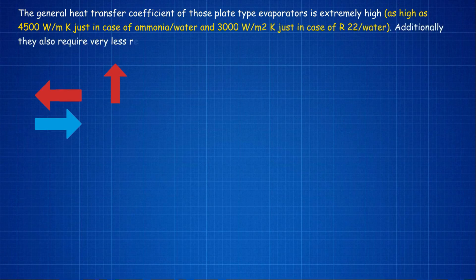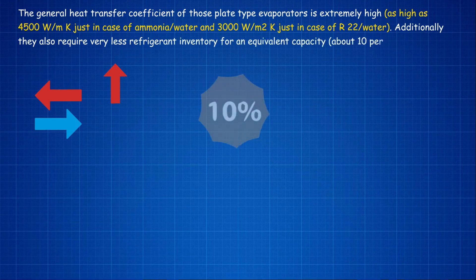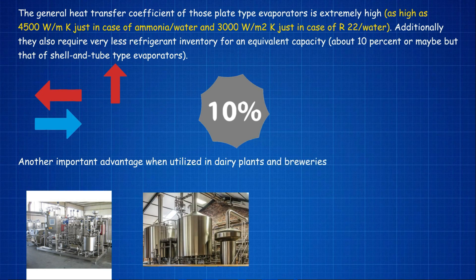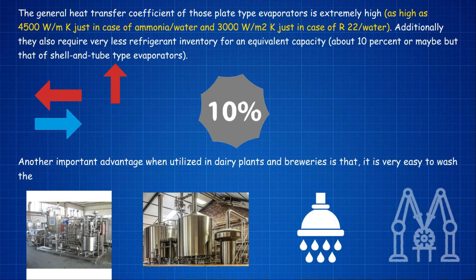Additionally, plate type evaporators require very less refrigerant inventory for an equivalent capacity — about 10% or maybe less of that of shell and tube type evaporators. Another important advantage when utilized in dairy plants and breweries is that it is very easy to clean the evaporator and reassemble it back as and when required.